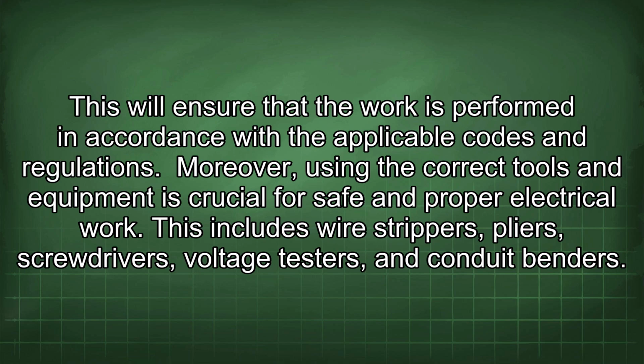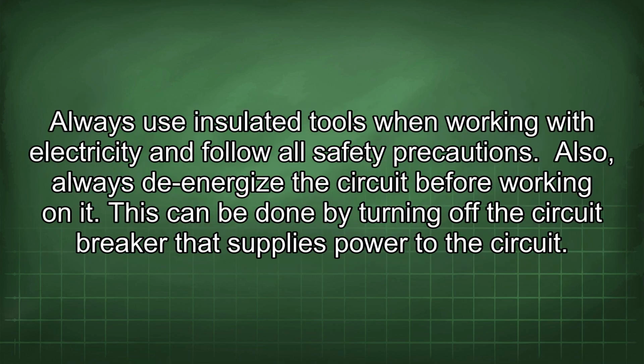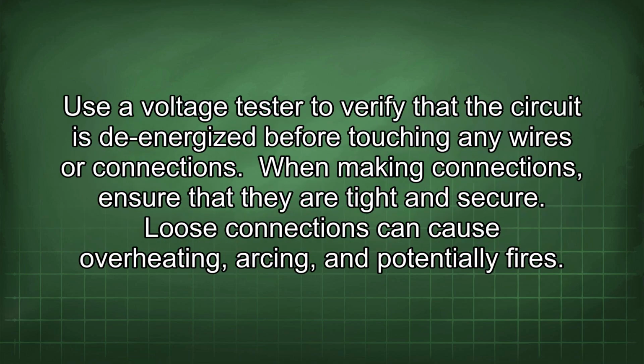Moreover, using the correct tools and equipment is crucial for safe and proper electrical work. This includes wire strippers, pliers, screwdrivers, voltage testers, and conduit benders. Always use insulated tools when working with electricity and follow all safety precautions. Also, always de-energize the circuit before working on it. This can be done by turning off the circuit breaker that supplies power to the circuit. Use a voltage tester to verify that the circuit is de-energized before touching any wires or connections.